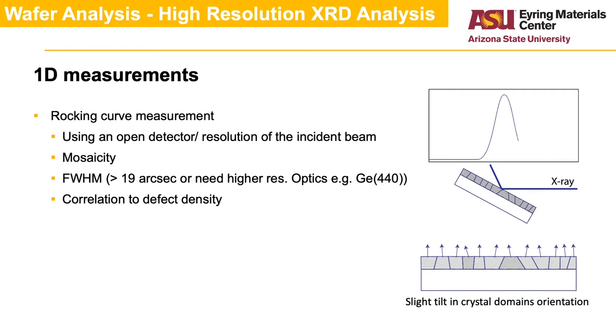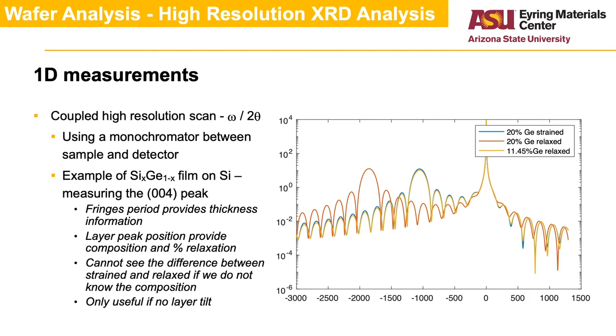This rocking curve measurement is always the first step when analyzing an epitaxial film. Once we are satisfied with the film's rocking curve, we can look at the coupled omega-theta measurement. Such a measurement can only be carried out on an on-axis peak — a peak which belongs to the family of the wafer's orientation. In this case, the substrate is used as a reference. During the measurement, we maintain omega, the X-ray incident angle onto the sample, at half the diffraction angle 2-theta. The period of the fringes provides the film's thickness.